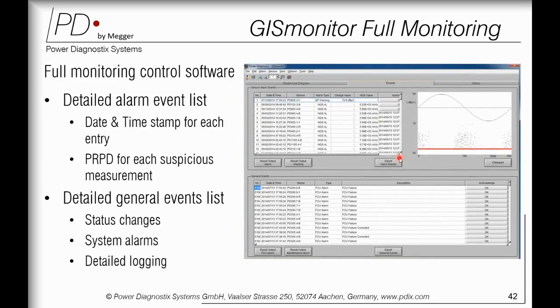It also has full monitoring control software with detailed alarm events. If something happens in your system, let's say PD, it always records the date and time stamp on each entry. So the PRPD for each suspicious measurement can be stored with the date, time, which phase, and which UHF sensors were involved. So you get complete details along with the PRPD patterns, along with general events like your system status, a connection getting loose, or the UPS battery not working fine. Anything that happens, everything will be logged in the software.